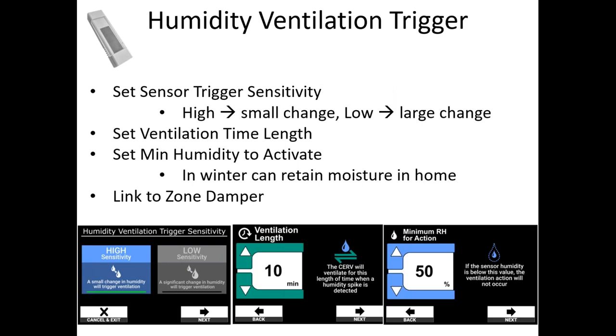As far as setting that up, you will select a high or low sensitivity. A high sensitivity would mean that a small change in humidity will trigger the CERV to ventilate, while a low sensitivity would mean you need a larger, more significant change to trigger ventilation. This is where you may use that for places with lower humidity levels versus locations with higher humidity levels, so climates that have lower humidity versus higher.